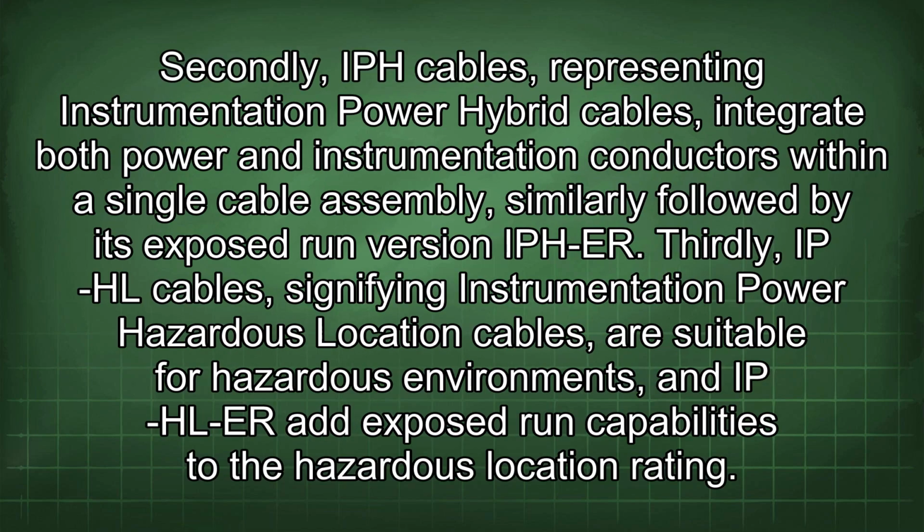Secondly, IPH cables, representing instrumentation power hybrid cables, integrate both power and instrumentation conductors within a single cable assembly, followed by its exposed run version IPHER. Thirdly, IPHL cables, signifying instrumentation power hazardous location cables, are suitable for hazardous environments, and IPHLER add exposed run capabilities to the hazardous location rating.